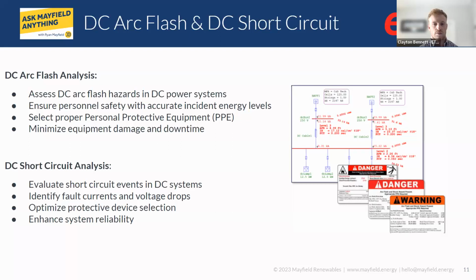As you can see in the picture on the right, we can see an intelligent one-line view with arc flash and DC short circuit values displayed. So really what we're doing here is for many different applications, including mission critical facilities, substations, battery banks, PV plants, nuclear plants, transportation systems, among the likes. Those are some of the main applications, but we're looking at the incident energy for direct current applications. Using these methods allows us to be fully compliant and ensures maximum reliability. And those include our maximum power calculation method, the Stokes and Oppenlander method, as well as the Paukert method. And these are used in conjunction by ETAP to determine incident energy and shock protection boundary calculations.